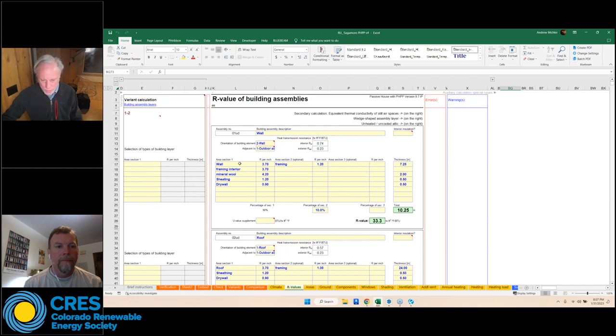This is how we put a wall system into the energy model. We put in the framing, then the R value of the wood, then the percentage of that — say 10%. Let me put a T-stud in, and let's say it has the same R value as our insulation. Right now we're at 33.3 total wall R value, and I'll put in 3.7 R value per inch. With the T-stud we go from 33 up to 37.